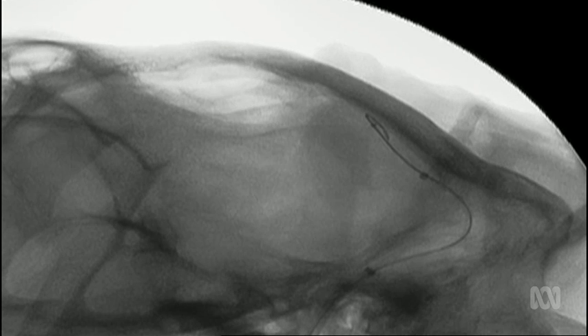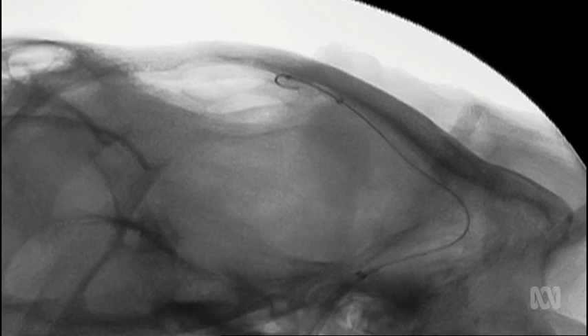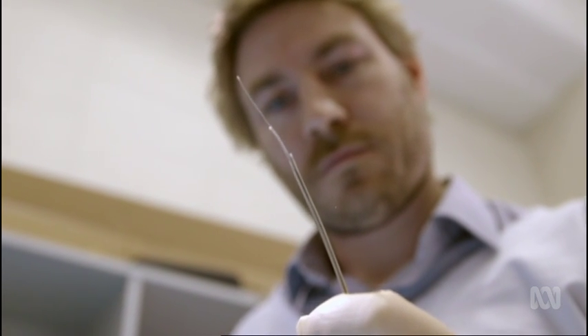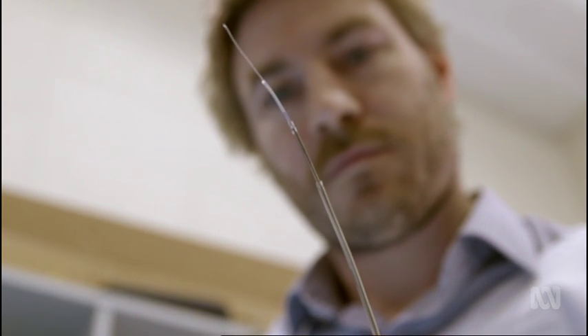But at the important end, right up close to the small veins, you have to have something extraordinarily soft and yet able to navigate and turn around corners. What we've had to do is combine numerous different sized catheters to enable us to take the sharp turns and bends.